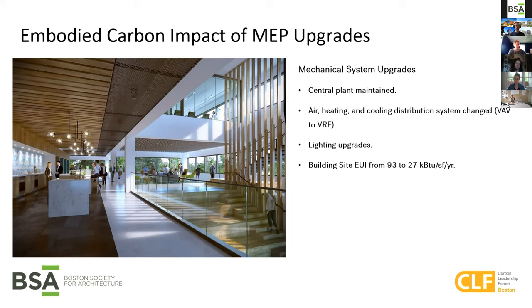So those mechanical system upgrades, like I said, we were able to maintain a fair amount of the actual equipment. The central plant was maintained. We simply switched the distribution system from a VAV, variable air volume, to a VRF, a variable refrigerant flow system. We did lighting upgrades. This project was built in 1984, and the lighting had never been upgraded, so that was a huge energy savings in updating to LED fixtures. Altogether, this brought our building site EUI from 93 to 27 kBTUs per square foot per year. So we cut it in about a third.